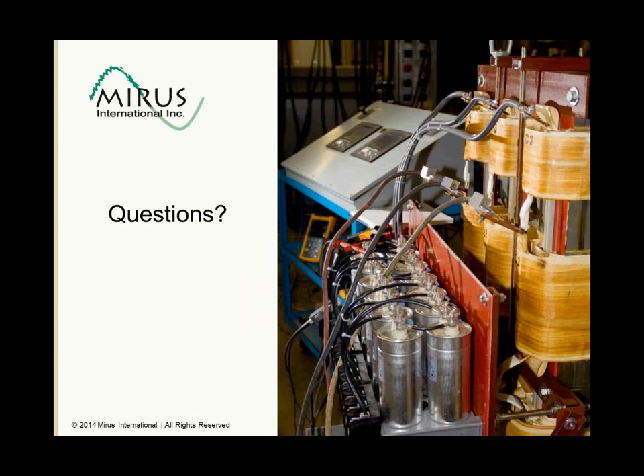Okay, I've got one question here related to the active filter example. It says, on the active filter example, you mentioned that high frequency harmonics introduced by the filter caused the premature power supply failure. Is that a typical result from the application of an active filter? And I would say yes, it is typical. It depends whether it'll cause problems with connected equipment because some equipment will be more sensitive to this very high frequency noise. But the amount of the high frequency introduced by the active filter will be dependent upon how good their input filter, or their LCL filter as it's referred to.